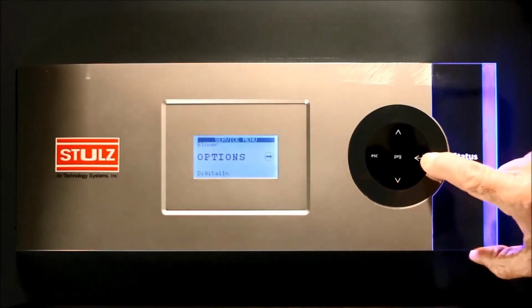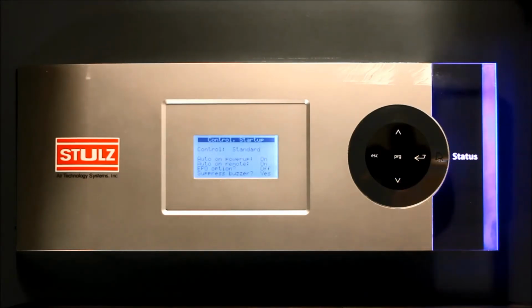Here you can make adjustments to various settings such as auto on power up, that when enabled the unit will come on automatically when main power is applied, auto on remote, this setting will allow a unit to be remotely switched on or off, and the EPO option, or emergency power off, that allows immediate shutdown without delays or minimum run times.